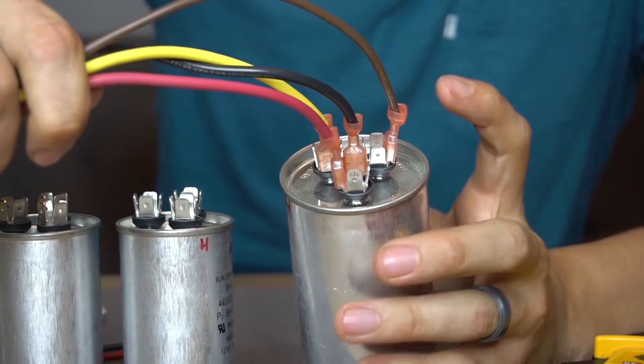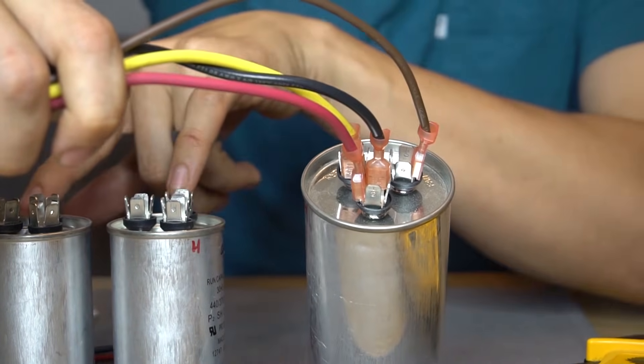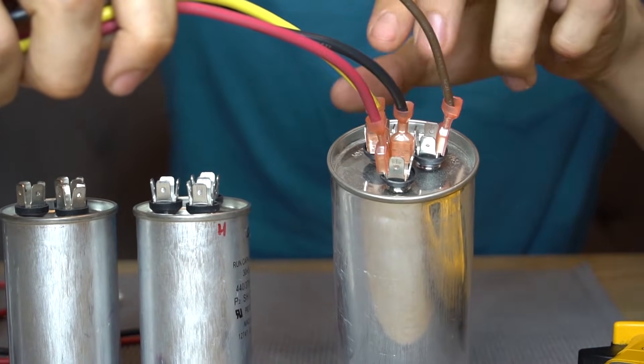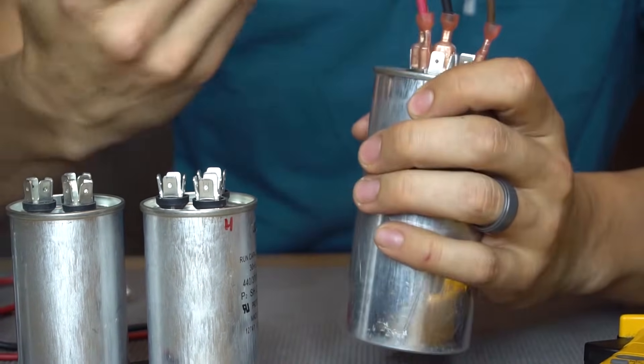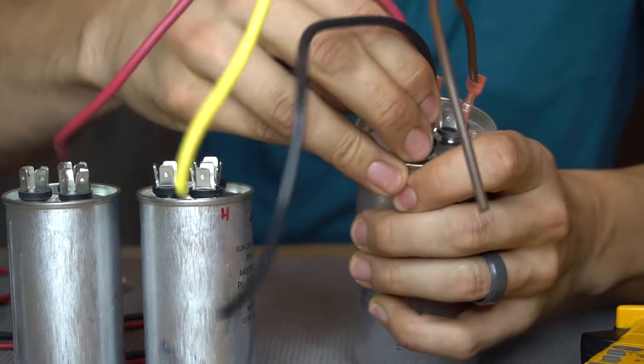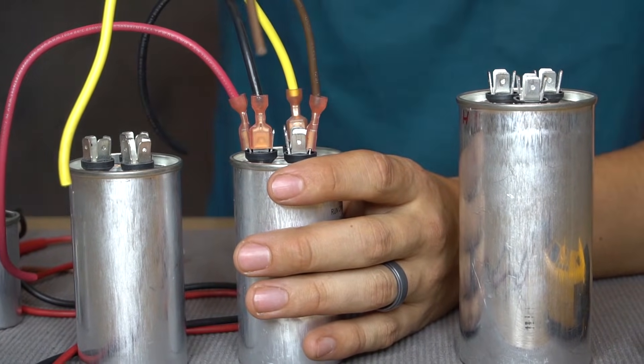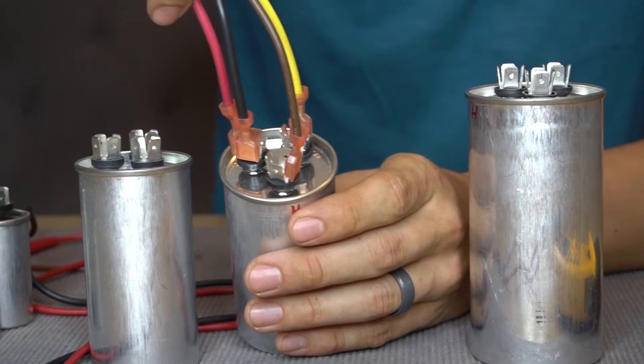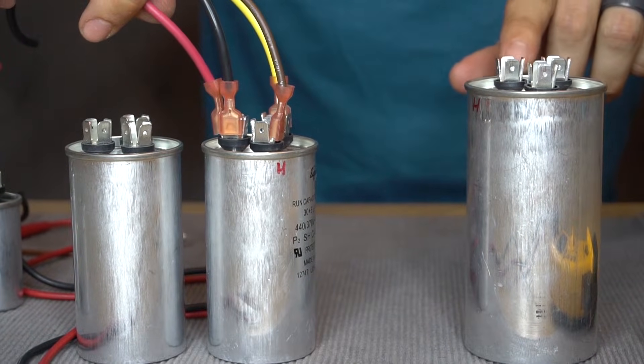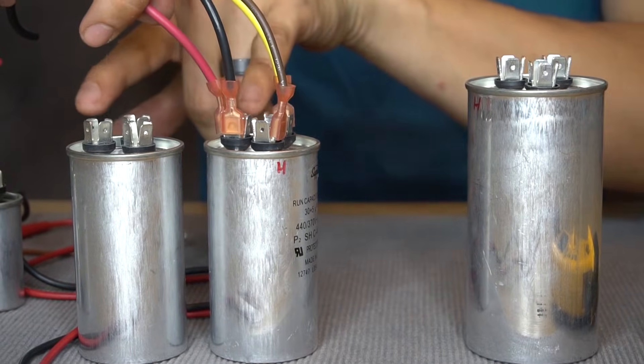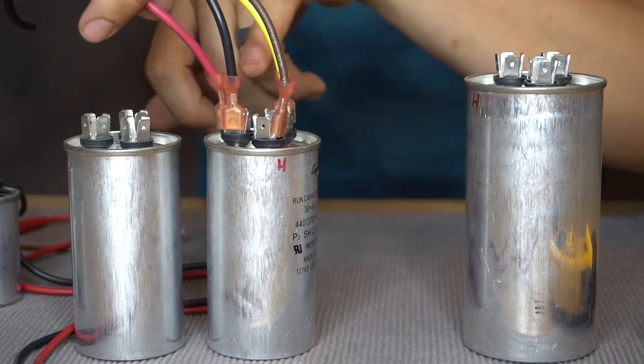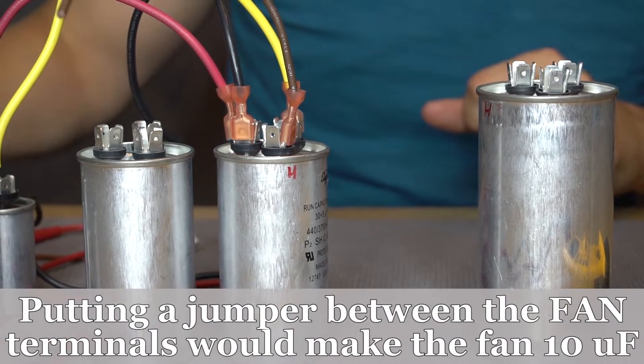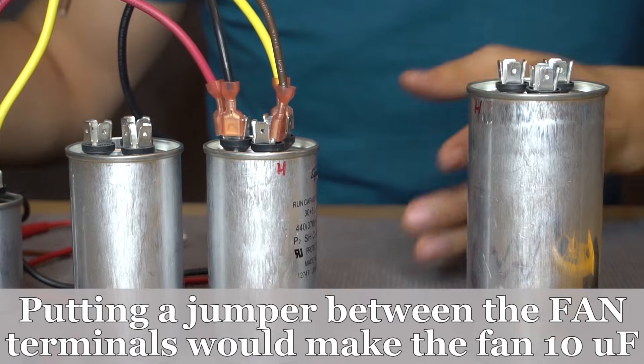So in order for you to take two 30 microfarad capacitors and turn it into a 60, you would basically transfer these wires to one of the 30s in the same positions. Okay, so I transferred all the wires from the 60 microfarad to the 30 in the same places, the herm, the common, and the fan. So I'm trying to create a 60 by 5 out of two capacitors that are both 30 by 5. So I just need to combine the compressor part and not the fan, so we're not going to touch the fan terminals at all.